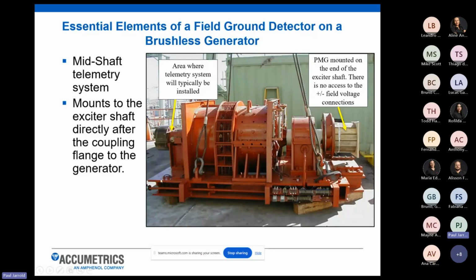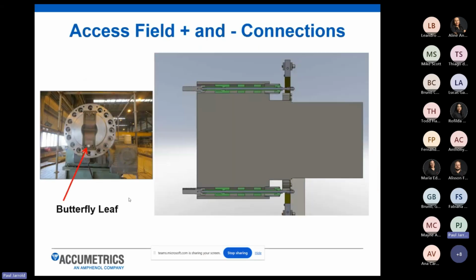So we have designed our mid-shaft telemetry system. It's a split collar design that's designed to bolt directly to the generator exciter shaft, and that gets installed near the coupling flange of the brushless exciter where it gets coupled up to the generator rotor. The next few slides will go into detail a bit more about what that looks like. But the first part of this discussion will be on the EFRAM mid-shaft system for larger machines.